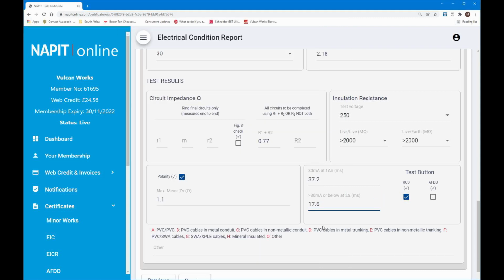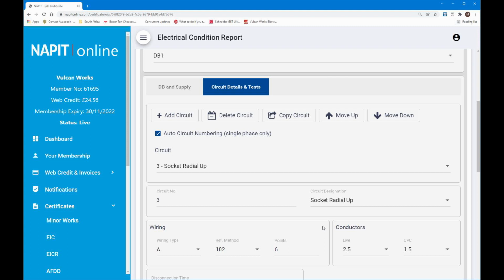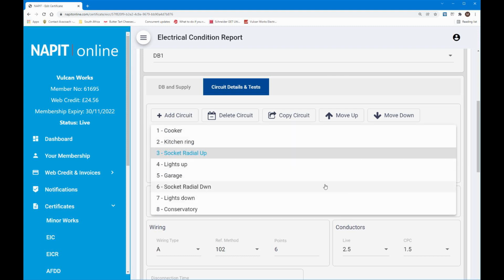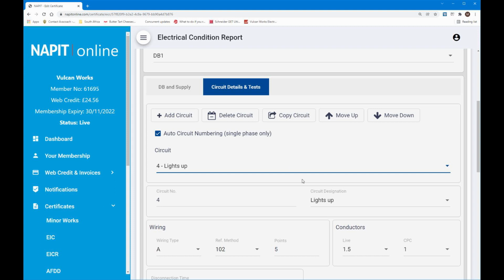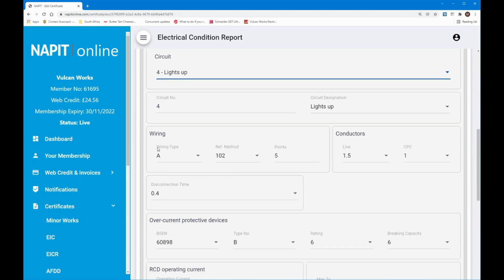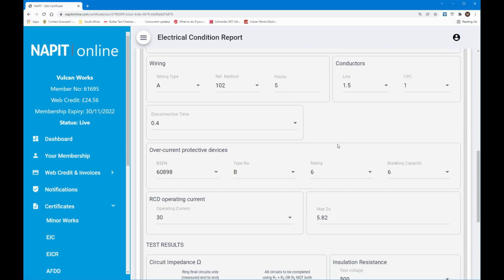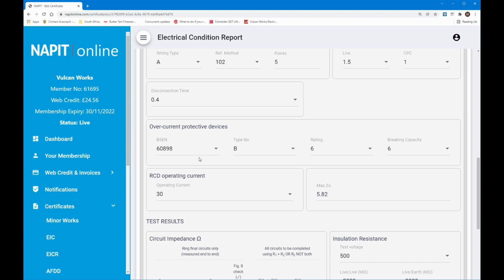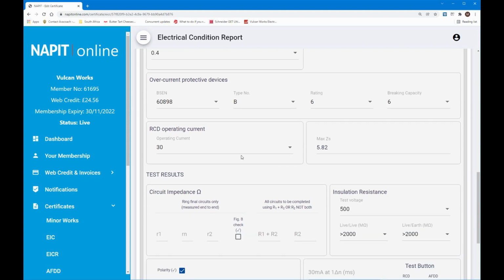Okay, let's move on to the next one. Let's do the lights next. Upstairs lights. Again, exactly the same type of wiring. There were 5 lights connected. It's a 1.5 and 1 because it's a lighting circuit now, 1.5 mil. Again, same disconnection time, same types of overcurrent protective devices, except this time it's a 6 amp MCB, and it's still the same breaking capacity. Same operating current for the RCD. This time the ZS for a 1.5 mil, for a 6 amp MCB is 5.82 for the ZS.